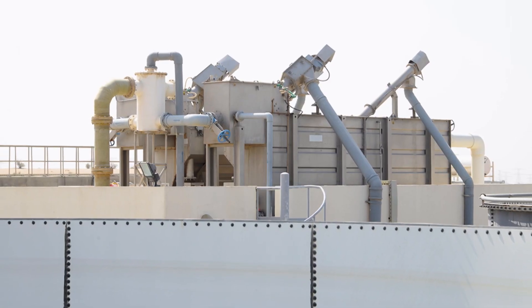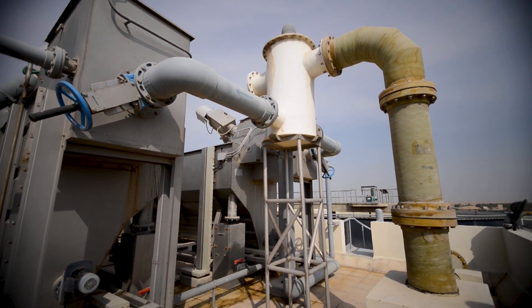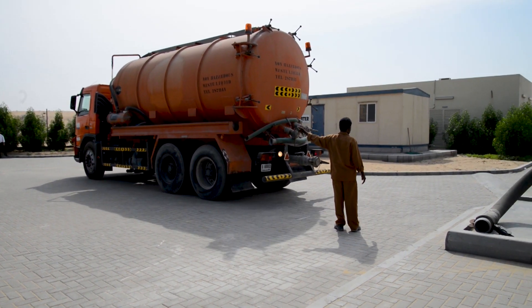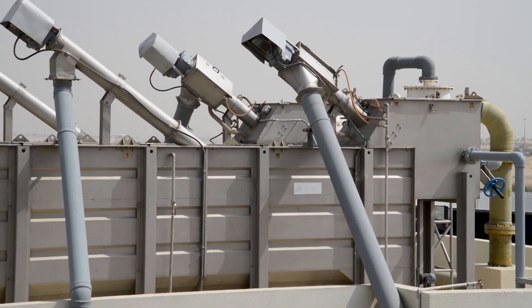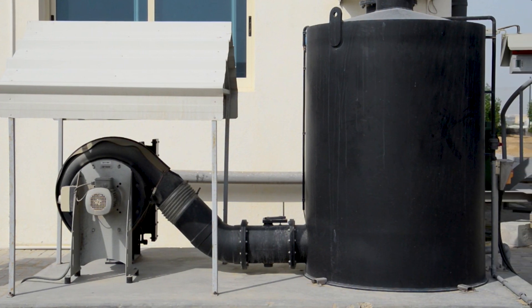The plant receives raw sewage from two sources. Sewage from the Alnabuda Labor Camp enters the pretreatment unit of the plant directly via sewer line. Septic tanks of individual residences are emptied by sewage tankers and transported to the plant's tanker station. This sewage is pre-screened by a packaged inlet screen and stored in an underground tank, which is then pumped to the main pretreatment section. This packaged inlet pretreatment unit effectively segregates screenings, grits, oil and grease. Foul air is cleaned by an odor control system.